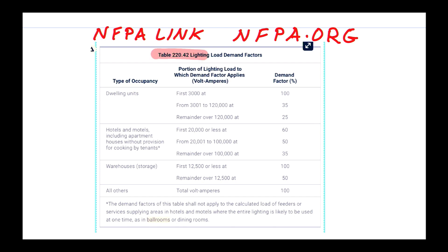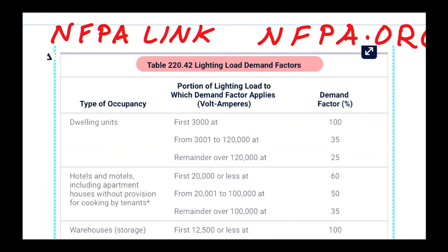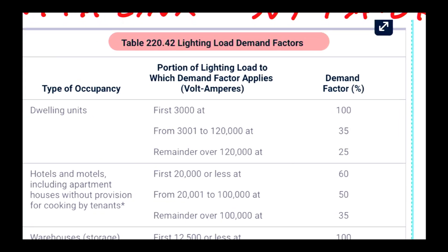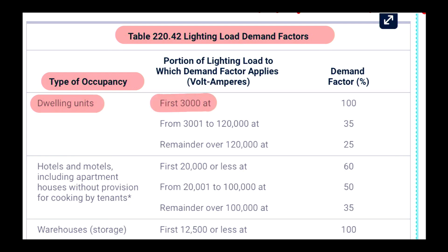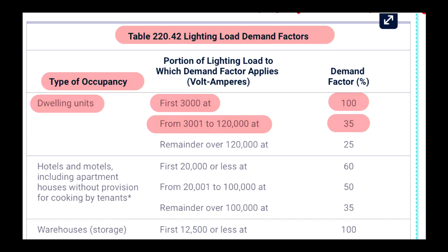In Table 220.42, the Lighting Load Demand Factors, we can see different types of occupancy. It's really important to get the occupancy right, because choosing the wrong occupancy means different demand factors and a wrong answer. For dwelling units: take the first 3,000 VA at 100%, then the next 3,001 to 120,000 VA at 35%, and then the remainder over 120,000 VA at 25%.